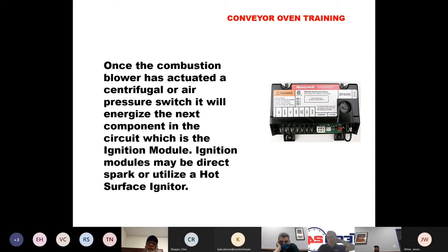All right, so once our combustion blower either actuates a centrifugal switch in it or a pressure switch that approves the rotation, the next component to be energized is an ignition module. And this ignition module may utilize direct spark, or it may have a hot surface igniter. Most of the world is direct spark. The only oven we see out there that is still using any hot surface ignition is Lincoln. The 1100 series Lincolns and the 1600 Lincolns are still using hot surface igniters.